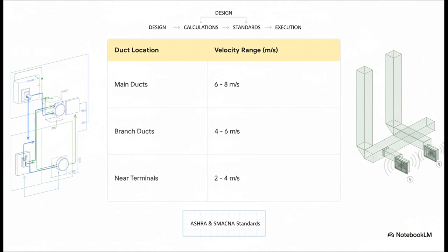Now, with a system like CLIMAVER, which is designed for low-pressure applications, two things are king: noise and efficiency. You don't want a system that sounds like a jet engine, right? So we turn to the industry standards, like ASHRAE and SMACNA, and they give us these recommended speed limits for the air.